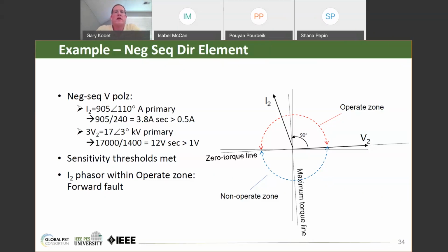Now, another method of polarizing that is used, and I should say that the use of negative sequence directional elements for ground faults is widespread, and one reason that it is used is that it is immune to zero sequence mutual coupling problems. There are other methods of determining ground fault directionality, and one of those is zero sequence voltage and zero sequence current.